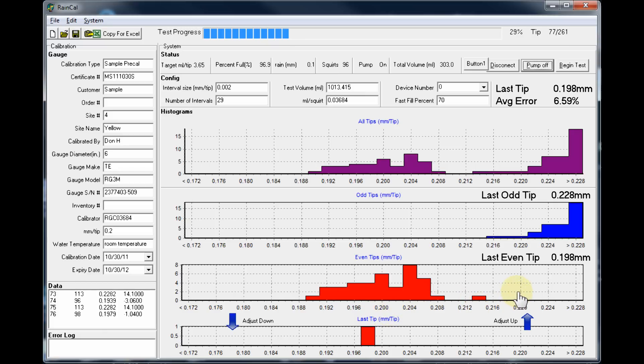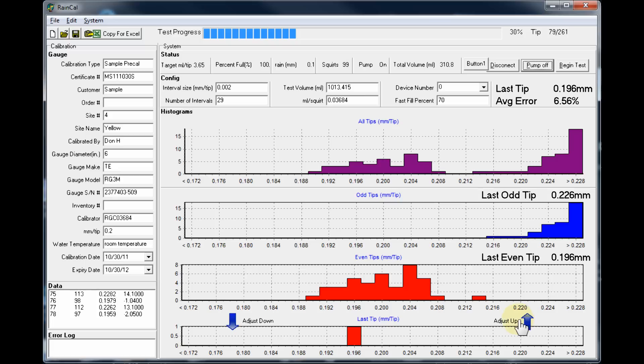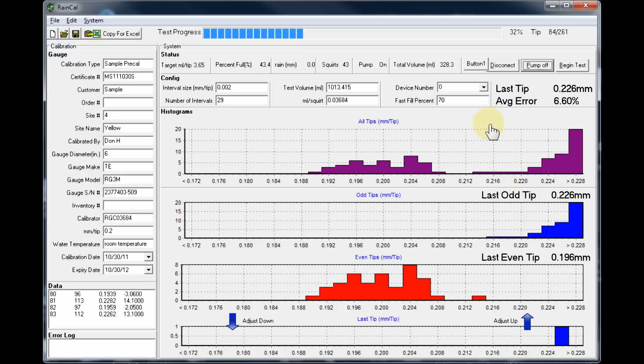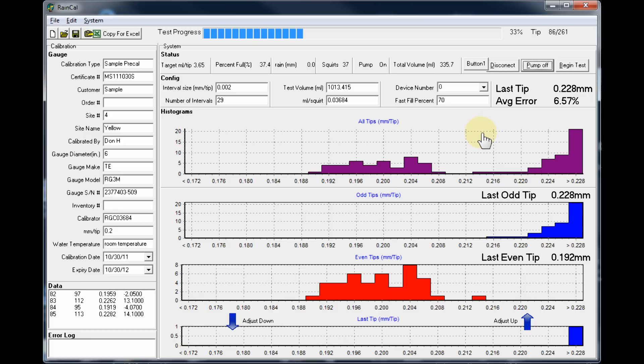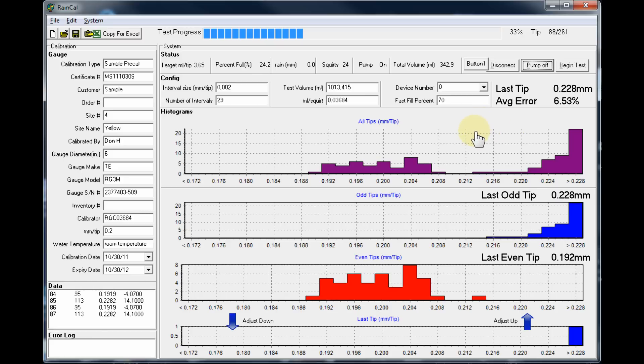We also can note that the arrow here will tell us roughly that we have to move the adjusting bolt on the tipping bucket gauge upward to bring it closer to the 0.2 calibration. This particular gauge has just come in from the field, so we're doing a pre-cal on it to see what the calibration information is like and to see how far off it is. If this factor was put into the previously recorded data, that would help to correct the data from the gauge which it had already recorded.